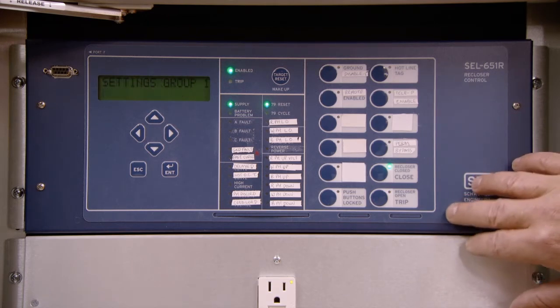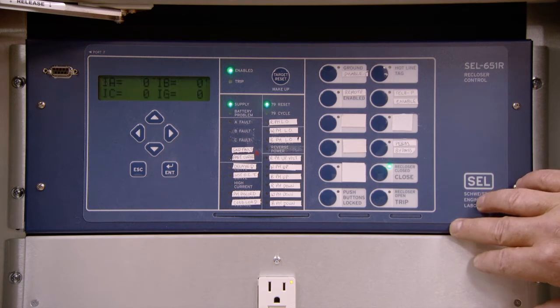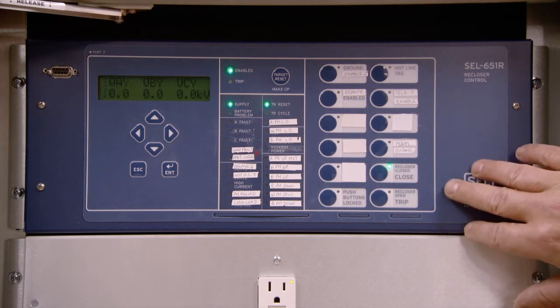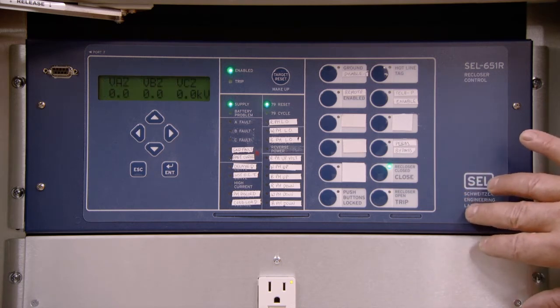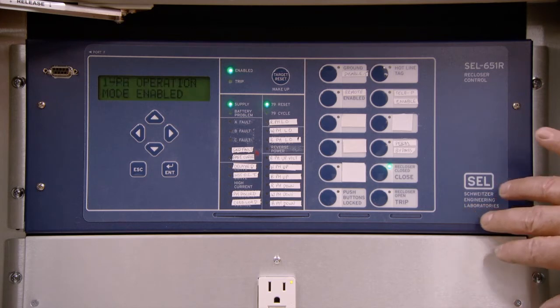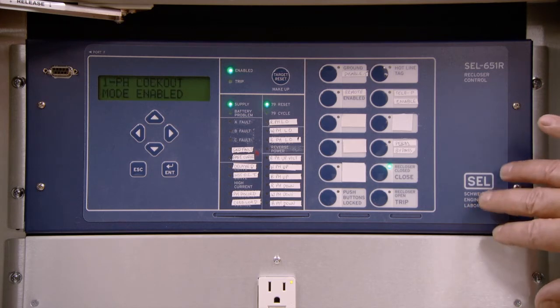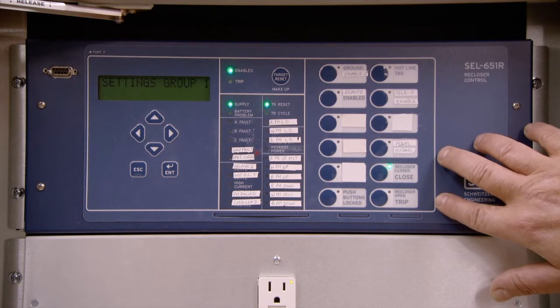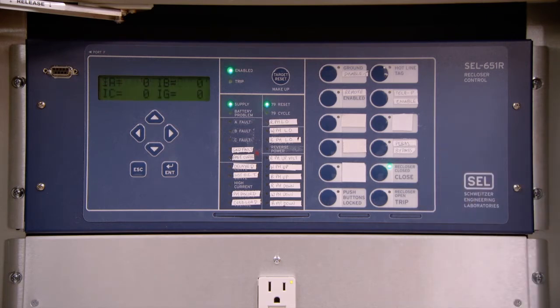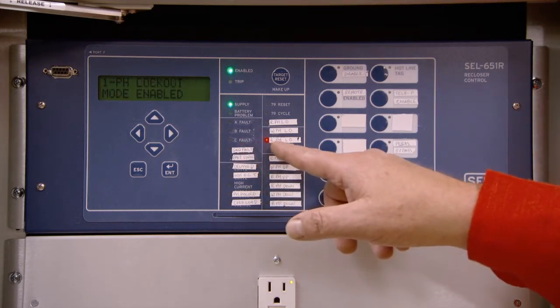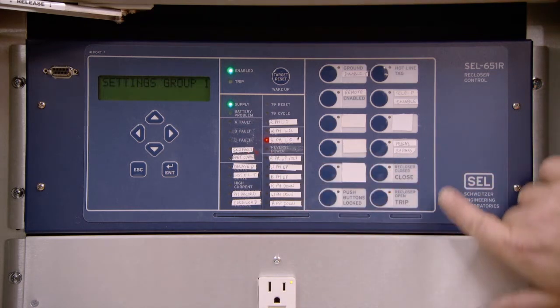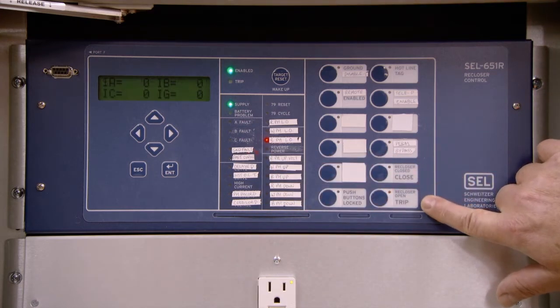If the unit has tripped out, what one should be aware of is an indication of what phase has gone out and what state it is actually in. If one were out in the field and one of the phases had faulted out, and remembering that this unit is set for single-phase operation, the panel will identify the phase that has faulted or tripped out. The control will also show you the current system status condition.